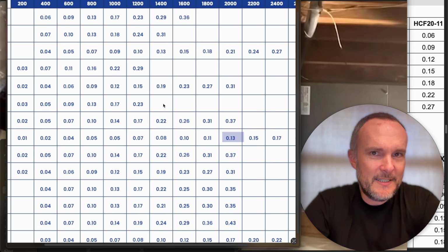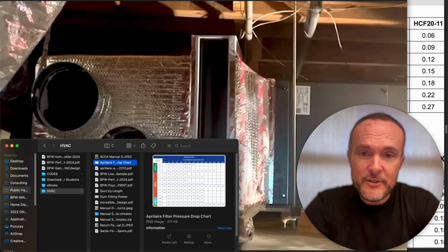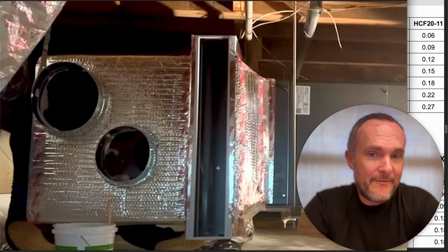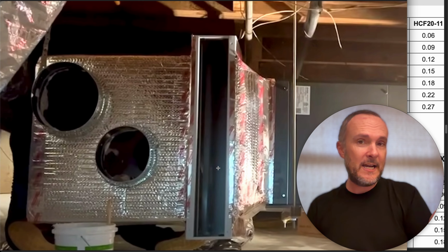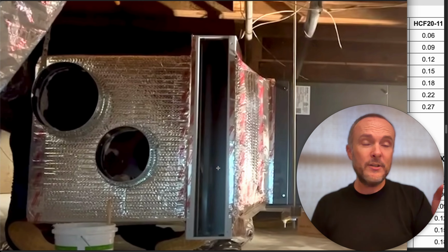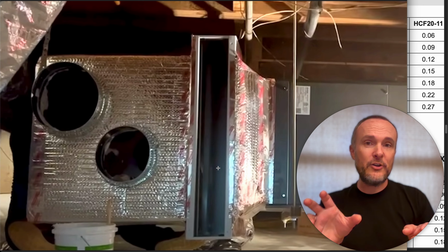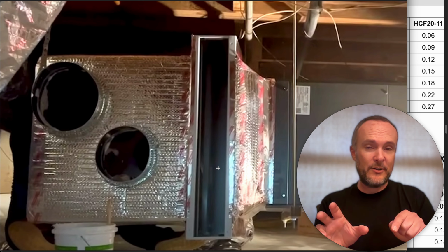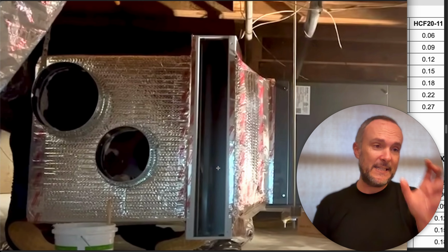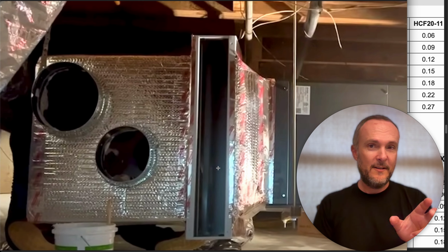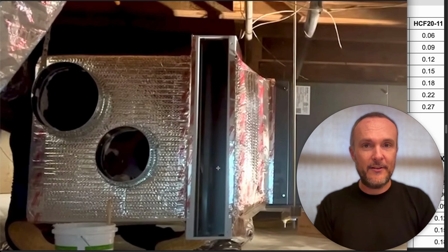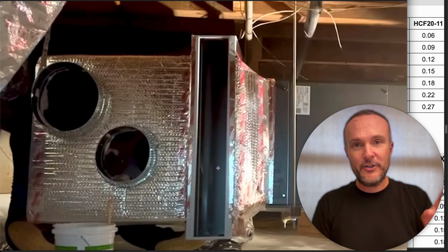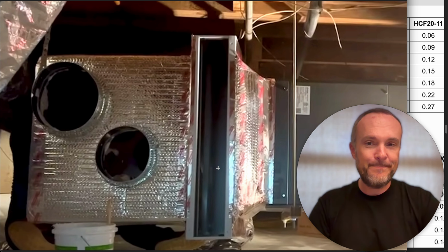And yeah, you're gonna need to make these custom transitions, but it becomes worth it because you have the ability to put whatever kind of filtration in there you want, and then you can run your air handler all the time if you want to get multiple passes and use a MERV 13. You get the same filtration level if you do multiple passes in an hour with a MERV 13 as if you do a MERV 16 and you do one pass per hour, which would be circulate mode on, like, 30 minutes out of each hour. I want the air handler to run, and it puts all the air in the house through the filter one time, and we get 95% capture. So I hope that that is interesting to people.